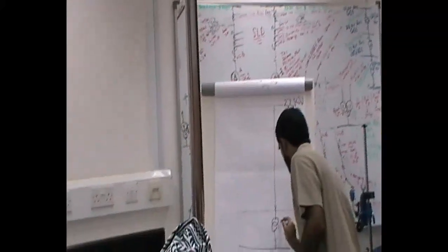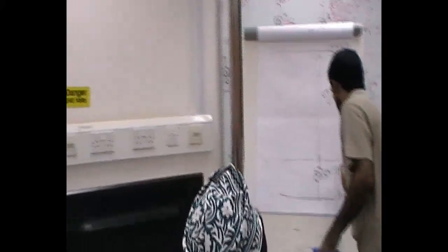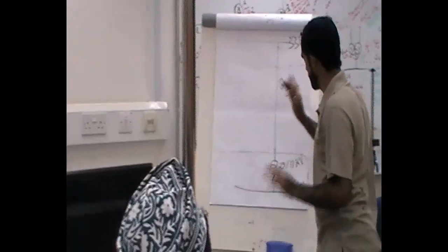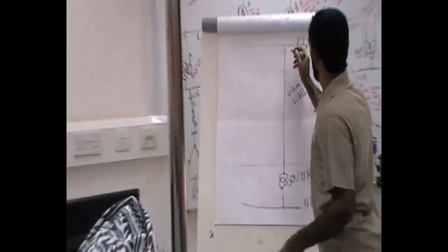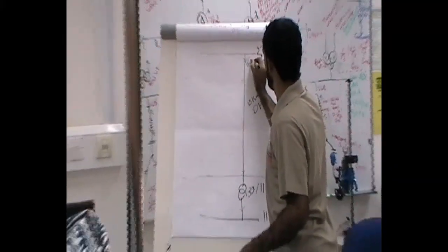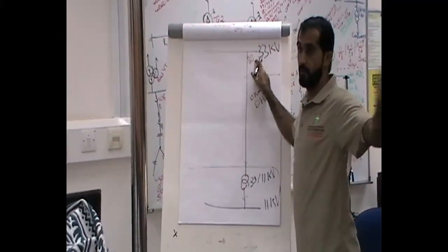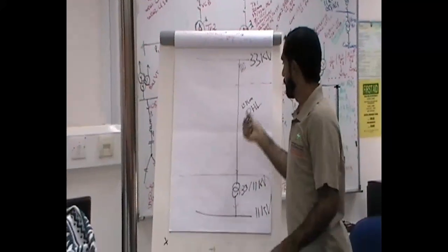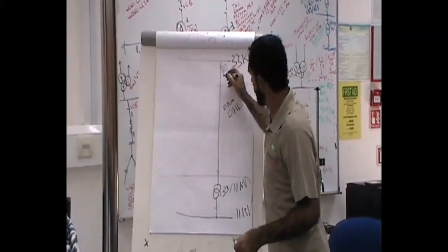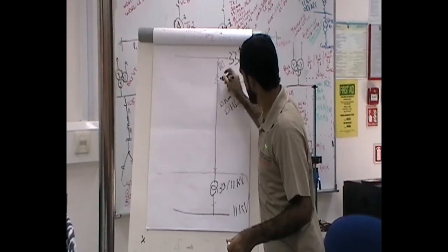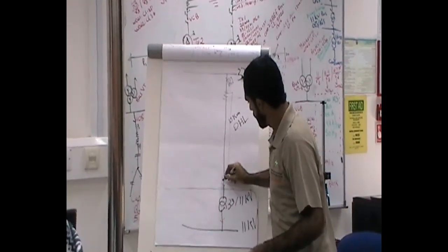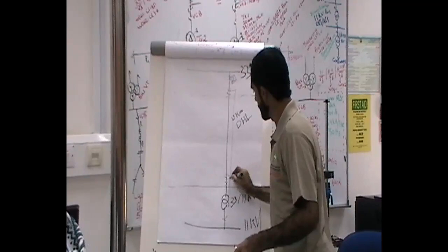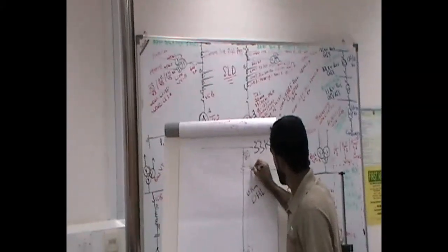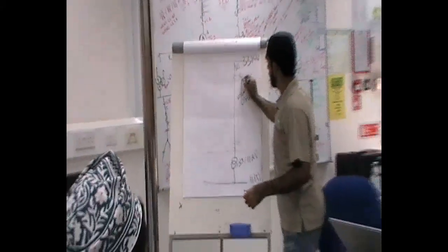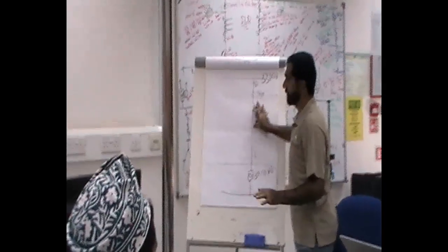What we are having is this transformer is 33 to 11 kV. Basically we have a 20 MVA, but it doesn't matter now. I have the relay here. Basically, if we have cable, we would have a fiber optic here and a CT here, and it will go through fiber optic from relays. This is a differential protection, 87, basically.